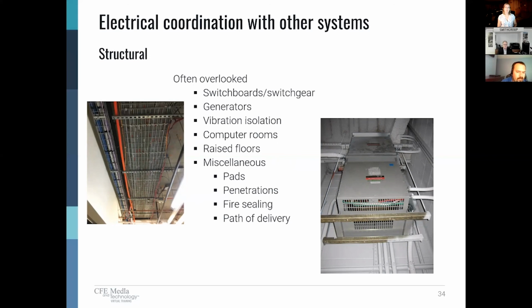Also, vibration isolation. An example would be a sensitive building where you've got sensitive adjacencies to the electrical gear, like research facilities, animal research facilities, vivarium spaces, those types of buildings, where you've got concerns about the vibration, basically leaking from equipment and traveling through the structural system into other occupancies. It's important that we isolate that, we coordinate that with structural. Of course, in computer rooms and raised floors, those things need to be coordinated with structural. Where you've got housekeeping pads under equipment, that adds weight.